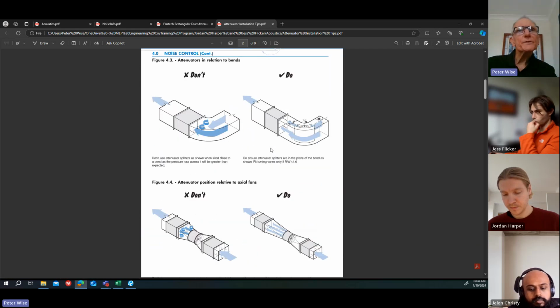This one is attenuators in relation to bends. The air's coming along, going around a bend, straight into the attenuator. You don't want to do that because the bend is causing turbulence. Now, there's another thing to notice here: on the left side, they've got the splitters in the vertical configuration. But over here, they've flipped the attenuator over on the right-hand side so the splitters are horizontal, and they've extended the length of the bend or put a straight piece after the bend so that the air can straighten out a bit before it goes into the attenuator.